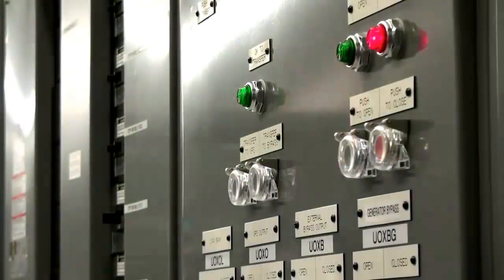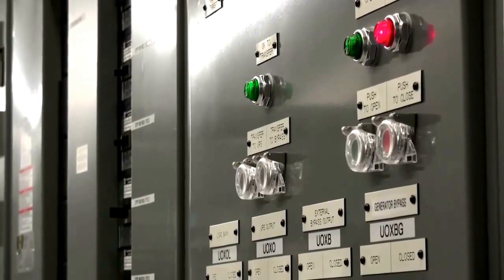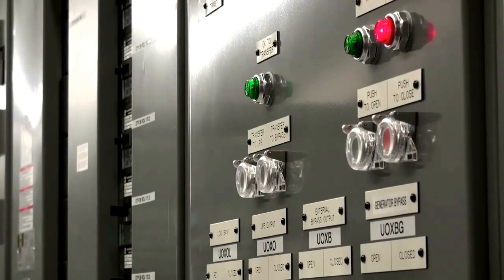The first patent is an isolated, redundant bypass system. It's a bus, and it's for both our generators and UPS. What it allows us to do is to move live load from one UPS to another UPS. So when we go on maintenance, instead of having to go on generators, we stay on utility power and we transfer the load to an entire separate UPS system, and then we do maintenance, and nobody else offers that. And it's a great thing for our customers because they know that their entire load is protected by UPS power.